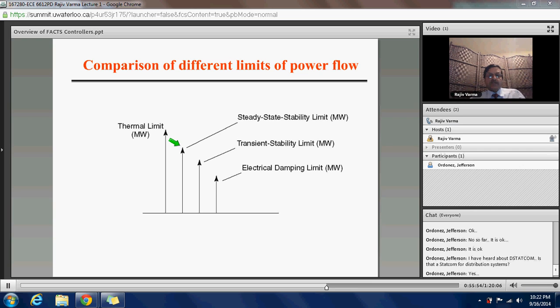But more often, what you see are faults. What you see are line switchings. What you see are transformer trips. What you find are large load changes. And then the transient stability comes into the picture. And then this limit that you are seeing is much lower than the thermal limit. This is much lower than the thermal limit.